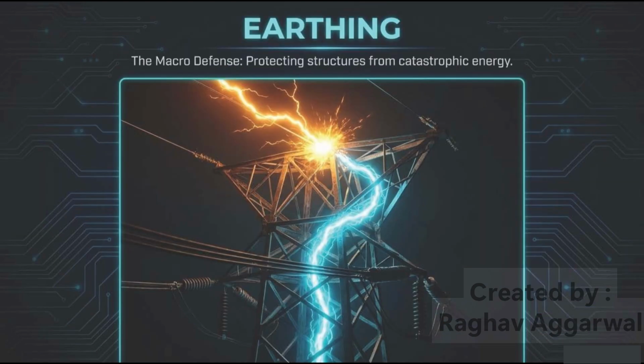Earthing is the plant's macro-level defense system. Earthing is designed to protect structures and equipment from catastrophic energy events. These include large fault currents and lightning-related energy that could otherwise damage equipment or endanger personnel. The illustration represents how fault energy is directed away from equipment and safely transferred into the earth. By providing a controlled path to ground, dangerous voltages can be reduced and the risk of electric shock can be minimized. In industrial facilities, earthing systems form part of the overall safety infrastructure.